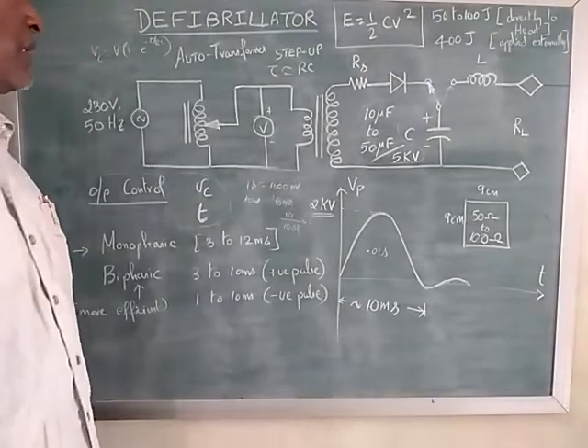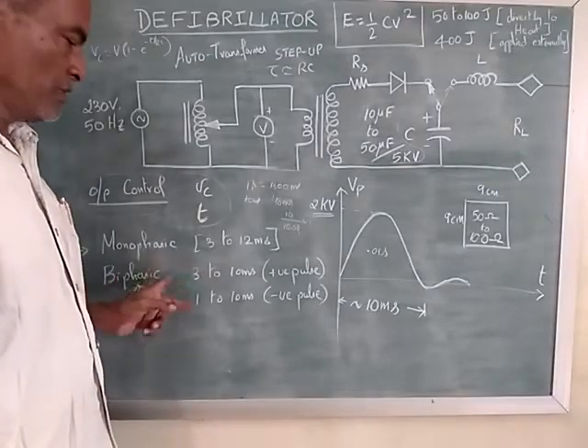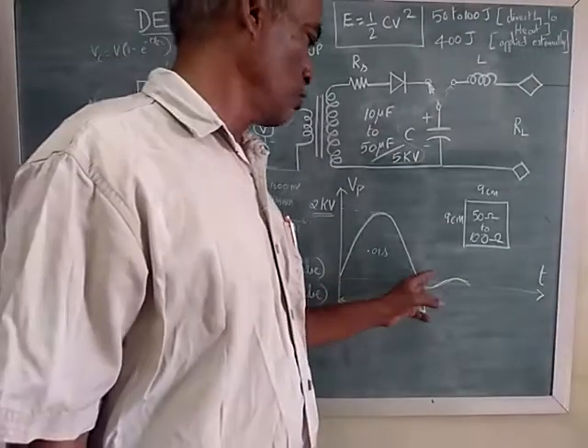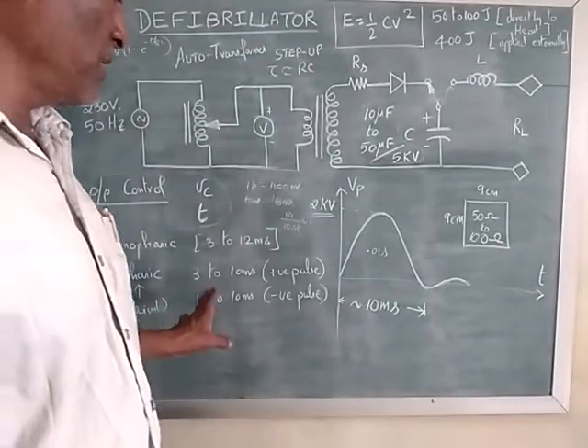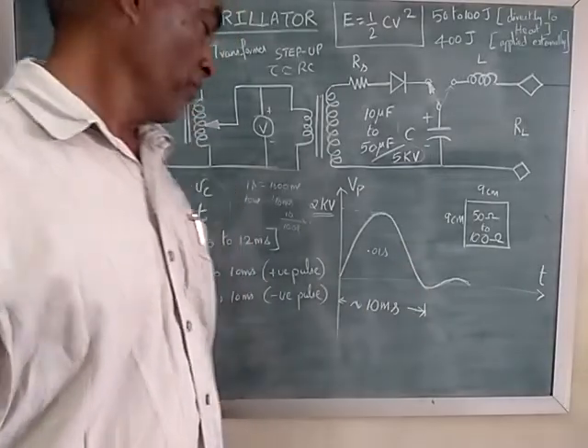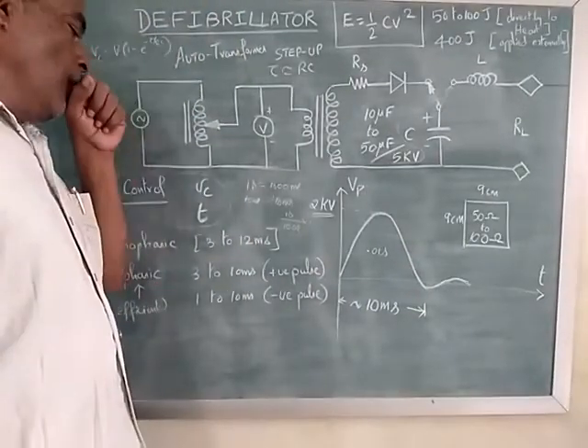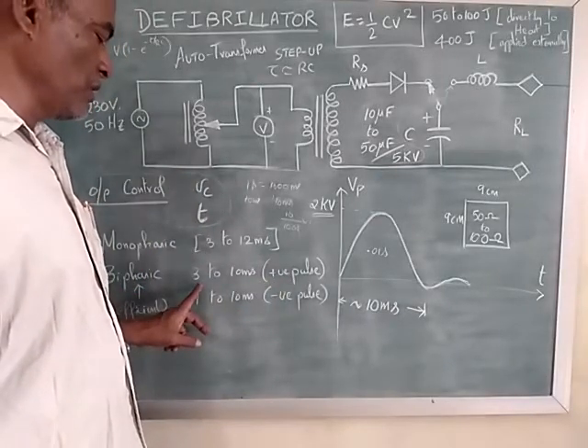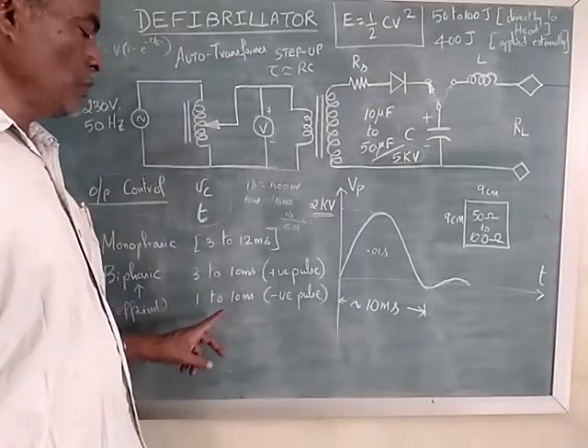So we have two types of defibrillator applications. One is monophasic. For this, 3 to 12 millisecond is the time. This can go from 3 millisecond to 12 millisecond. We have biphasic. In biphasic, we have positive pulse as well as negative pulse. So biphasic, if it is a positive pulse, it goes for 3 to 10 millisecond. If it is a negative pulse, it goes for 1 to 10 millisecond.